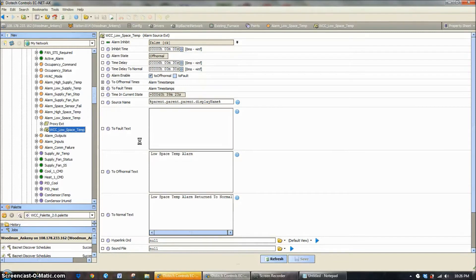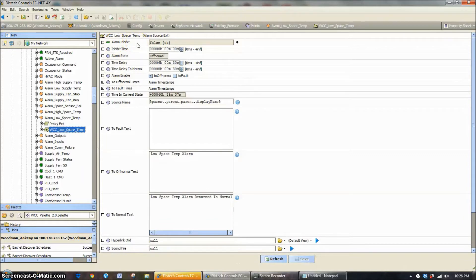In this case, this one was going off way too often — you saw 54 times. I've already gone through and made the time delay change just recently, which is why I decided to make this video. I'm going to briefly explain all the different pieces of this alarm extension. The alarm inhibit is used to essentially disable the alarm — if you want, for example, in the middle of the night you don't want an alarm to go off, we could tie that to a schedule. The alarm state: all alarms within the Niagara system are either normal or off-normal, not normal and in-alarm like you would expect.